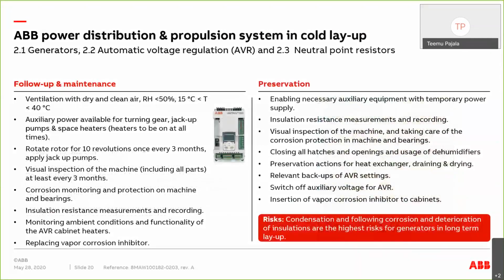Then we go through the equipment. So first we have generators, AVRs, and NP resistors. For generators, the same instruction as for warm layup: the shaft needs to be rotated every now and then, at least every 3 months, 10 revolutions for the shaft, using jack-up pumps.